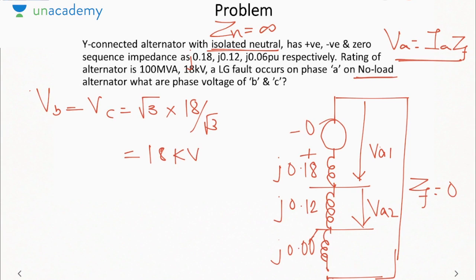Now if you see here, the phase voltage magnitude becomes equal to the line voltage if the neutral of the system is left isolated. That means high voltage will be induced in the transmission line if you do not ground the neutral of the system. That is why we need neutral grounding to avoid high voltages. So ungrounded neutral has high voltage.